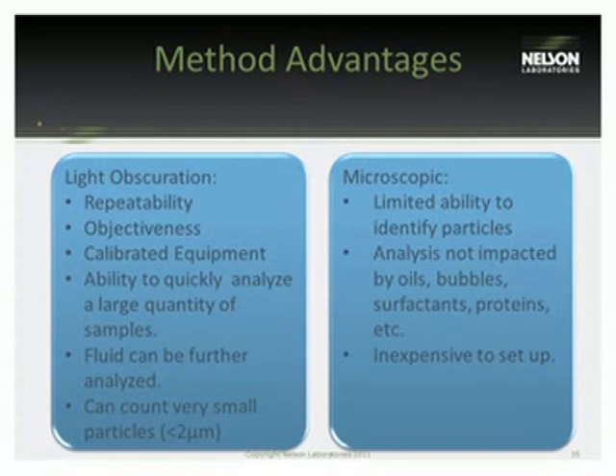The microscopic also is not impacted by any oils or surfactants, bubbles, any sort of biological particles, proteins, or anything of that nature. We test quite a few biological products here, plasmids and different vectors and things that may cause problems with the light obscuration counter, or the liquid particle counter rather. And the reason that those compounds cause problems is because the liquid particle counter essentially is kind of like a Coulter counter in a way.